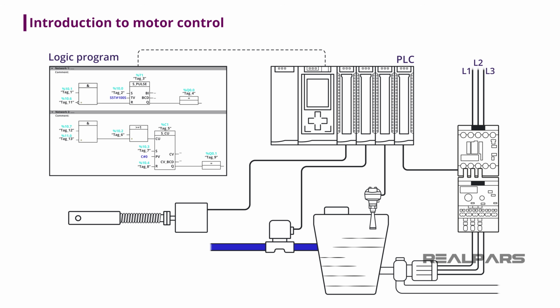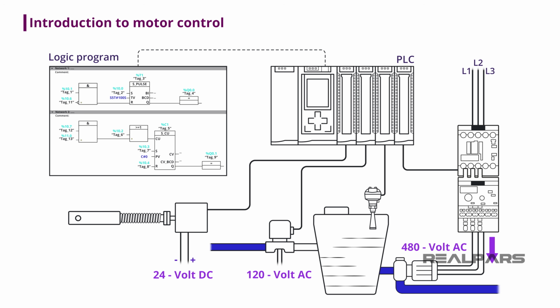As automation engineers, we write logic programs for PLC and DCS systems that monitor process variables, open and close valves, set control loop modes, and start and stop motors for pumps, compressors, and conveyor systems. Most digital outputs on control systems operate on 24-volt DC or 120-volt AC. So how do I start and stop three-phase 480-volt AC industrial motors?